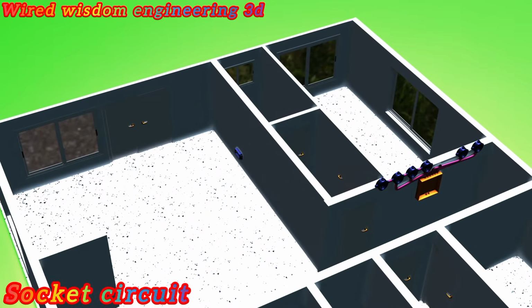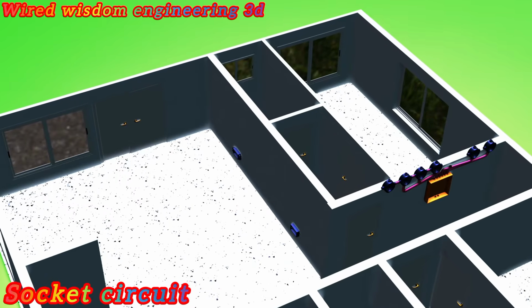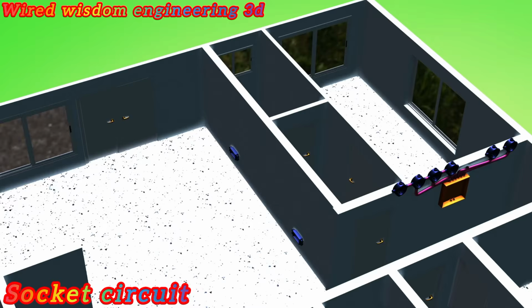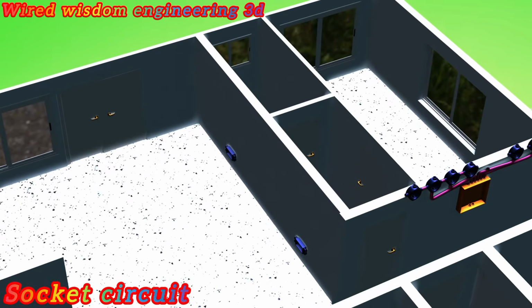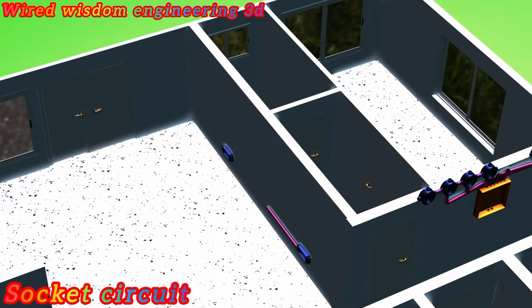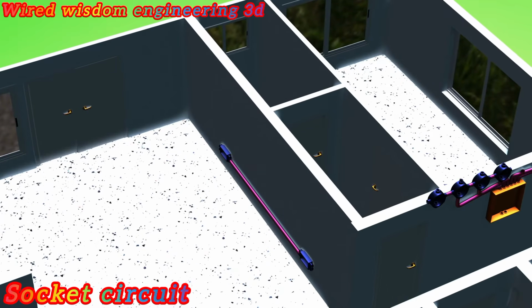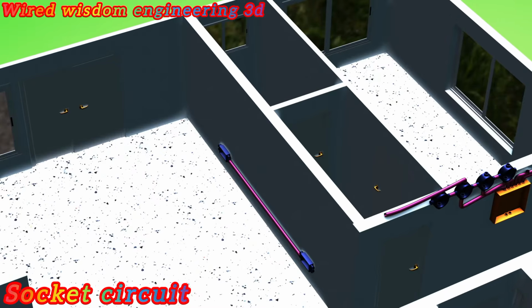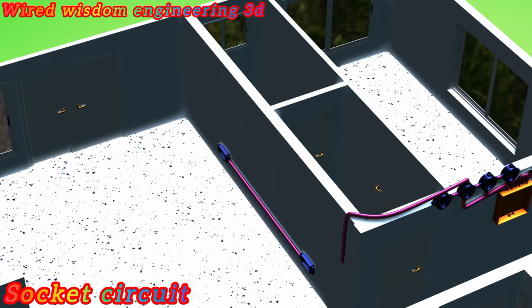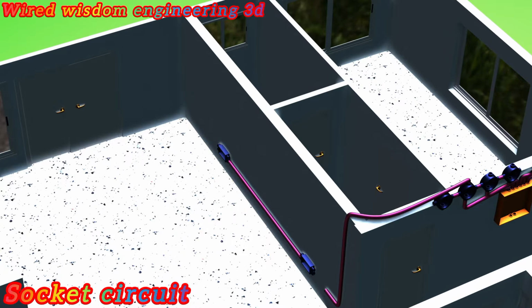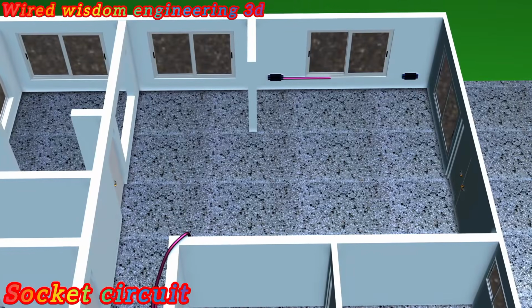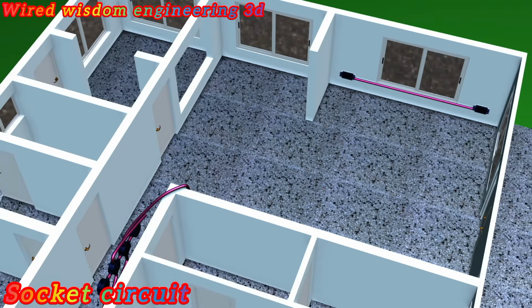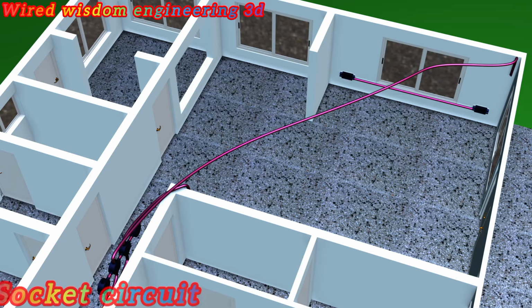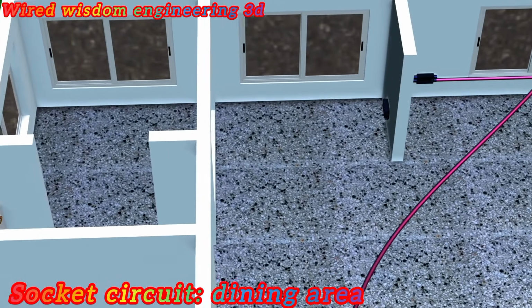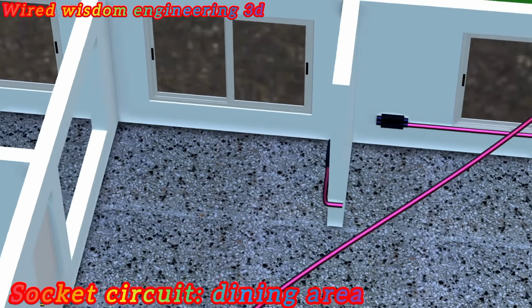Socket circuit conduit layout. The first major circuit we address is the socket outlet circuit. Starting in the sitting room, electrical conduits are linked from one socket point to the next, creating a continuous and logical path. From the consumer unit, a conduit feeds into a circular junction box. From this junction box, conduits branch out to the sitting room sockets. Opposite wall sockets are routed in a similar manner, ensuring balanced distribution and neat cable management. Sockets in the dining area are linked directly to the sitting room socket circuit, allowing shared distribution while maintaining accessibility.